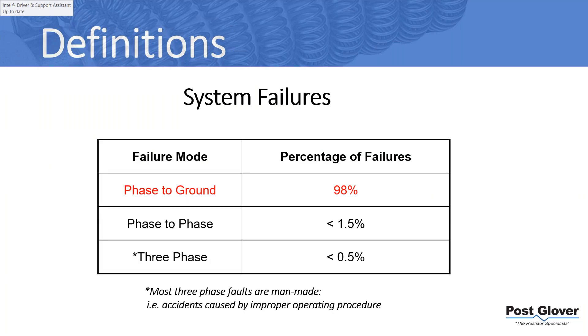Looking at an industrial study of system failures, the point is that the vast majority of all your faults are phase to ground. That's important because when we talk about resistance grounding, which uses a neutral grounding resistor connecting between the neutral and the ground, we're impacting the phase-to-ground portion of that system. So that 98% is what we deal with.